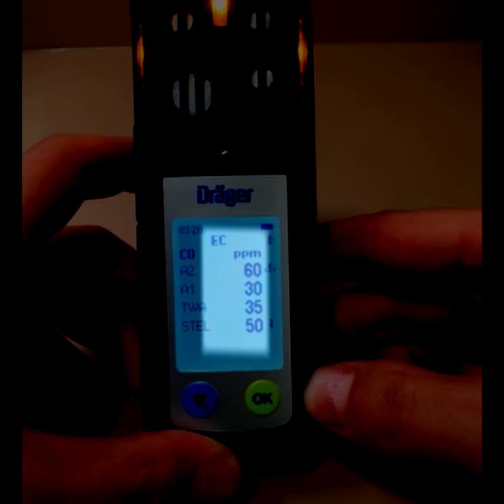Next, you have your CO sensor or carbon monoxide sensor with a two-alarm system. Alarm 1 is set at 30 parts per million. Alarm 2 is set at 60 parts per million. You can also see your time-weighted average, which is set to 35 parts per million, as well as your STEL, or short-term exposure limit, set at 50 parts per million.